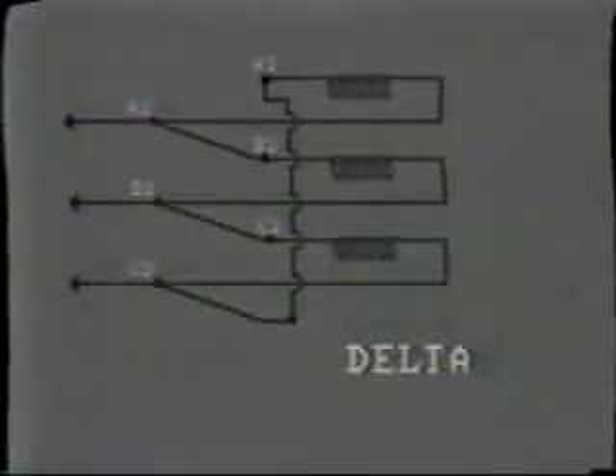Diagrammatically, this Y connection is commonly shown like this. A1, B1, and C1 are connected together to form the neutral, and A2, B2, and C2 are connected to the power system. And here we see the terminal connections for the delta arrangement. Check through this connection in detail in your workbook. Again, this may be shown diagrammatically like this. Obviously, with the delta arrangement, there can be no common neutral and therefore no connection to ground.